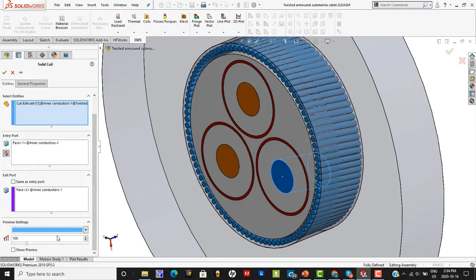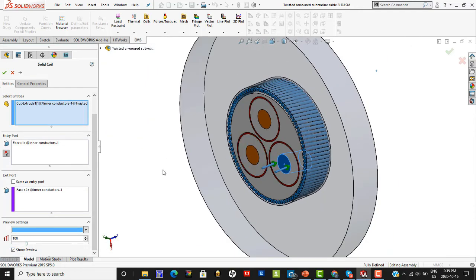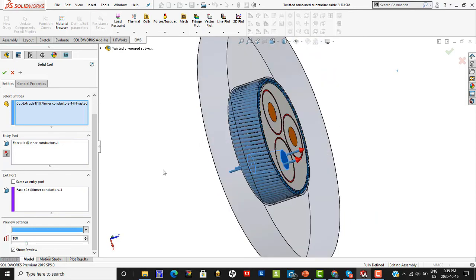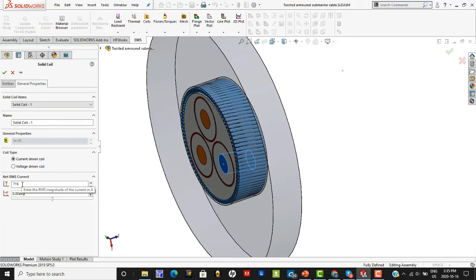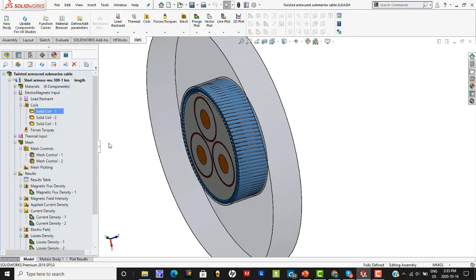The conductor carries current — you can see the current enters on the left and leaves the model on the right side as denoted by the arrows. Once you define the current, you need to specify the RMS value and the phase angle. Because we have three conductors carrying current at three different phases, you specify the phase shift between the conductors: 0, 120, and 240 degrees for the three conductors. Similarly, I have defined coils for the second and third conductor.